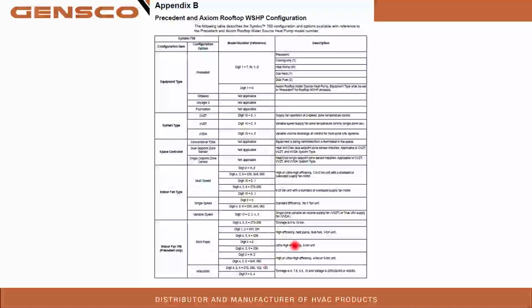So this is all your configuration type in that general configuration, all your equipment type, your fan type or system type CVZT. This is everything that you could select, conventional T-stat, indoor fan type. Make sure you put multi-speed. If you have it at single speed, you'll prompt an alert because it knows that it's a multi-speed. Indoor fan VFD. So there are some cases where we didn't have that EBM. That EBM Pabst is that plenum fan. So that is a variable speed plenum fan.